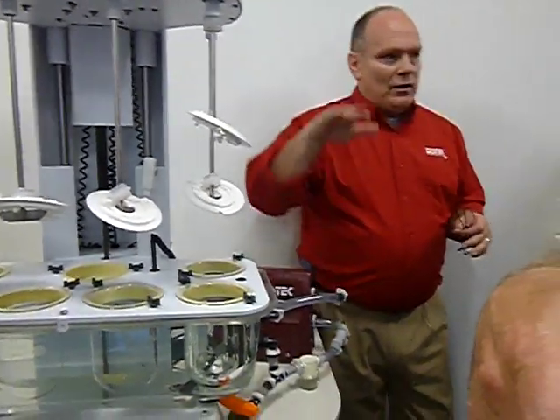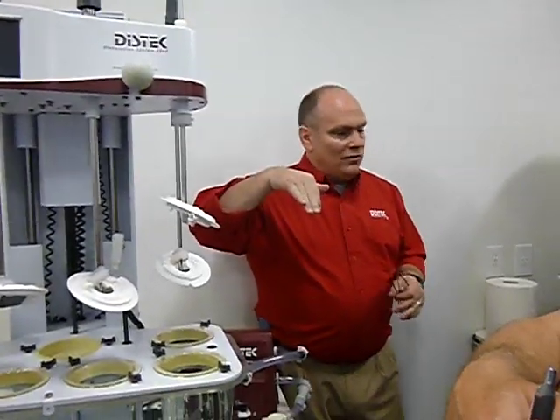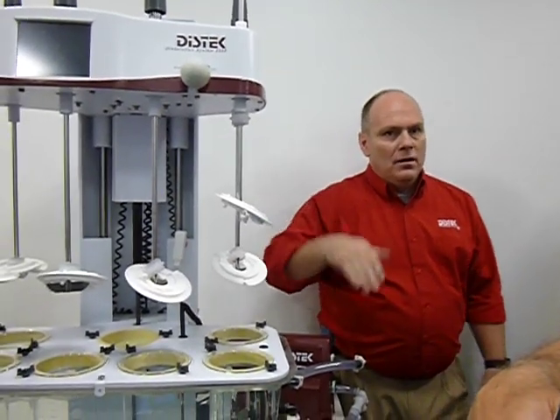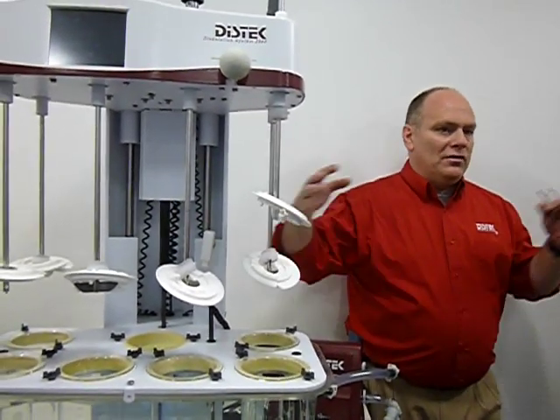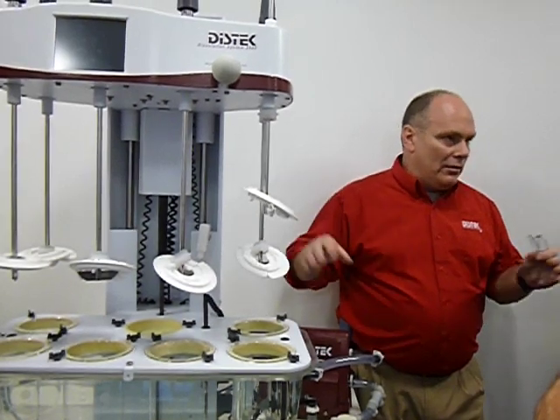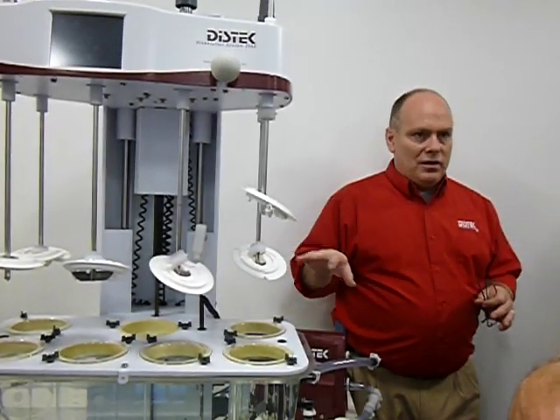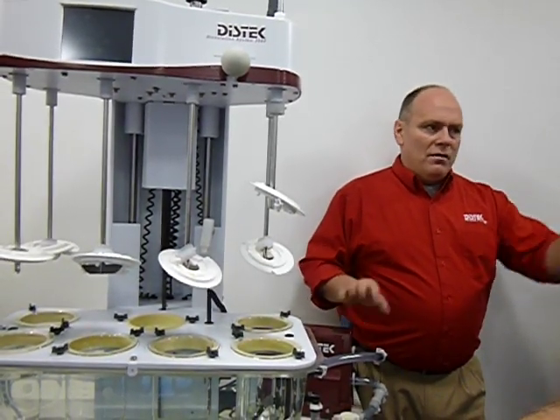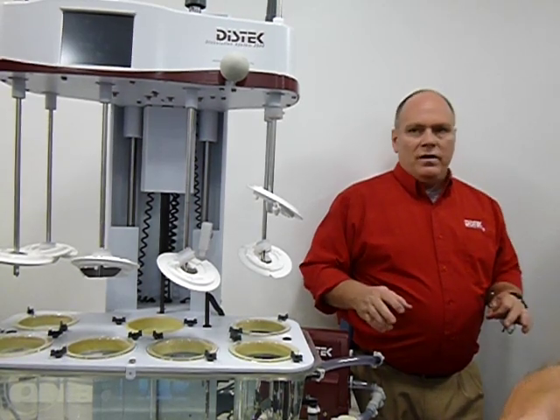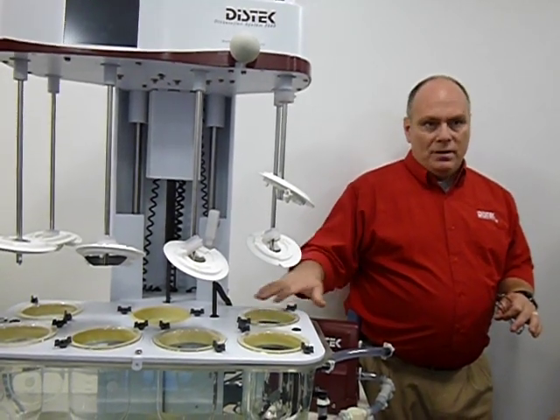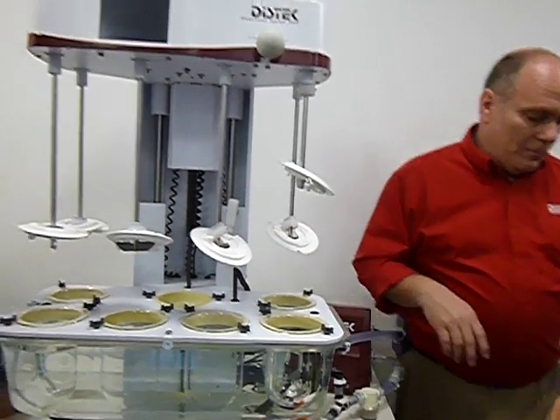Varian does it with theirs. They have a little wire screen on their bath where it comes out, so when it hits against it, it deflects to the bottom. But we have to make sure that it thoroughly still circulates the media around so that all the temperature stays the same. But again, on that one over there, very minor changes between one and the other. This one here, maybe a little bit more because of the issue that we've seen. But we'll get to that when we start working on that one. Centering.